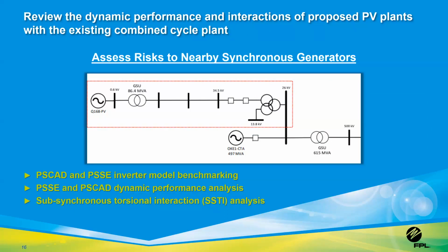We were concerned about torsional interactions that could potentially damage the generator shaft. Therefore, we performed a detailed EMT analysis. We validated all the models, benchmarked our transient stability analysis results, and we performed things like SSTI, subsynchronous torsional interaction analysis, that we couldn't do with other tools. And we were able to demonstrate that there was no risk to the plant. Next slide, please.